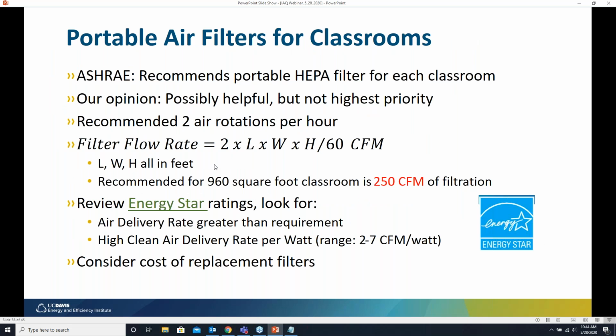ASHRAE is also recommending portable HEPA filters for each classroom. This is possibly helpful, but I want to caution it's not the highest priority. If you do decide to get portable filters, for example, maybe these are in classrooms that you can't have central filtration or something like that, then you want to achieve at least 2 air rotations per hour. That would be approximately 250 CFM of filtration for a classroom.